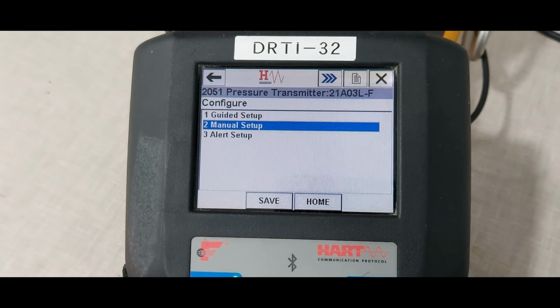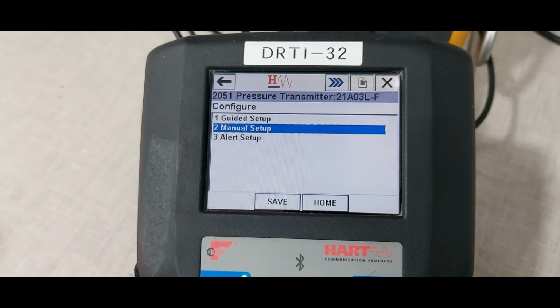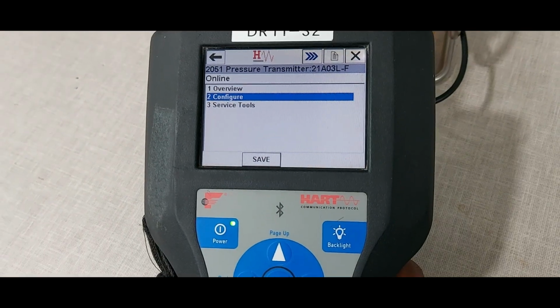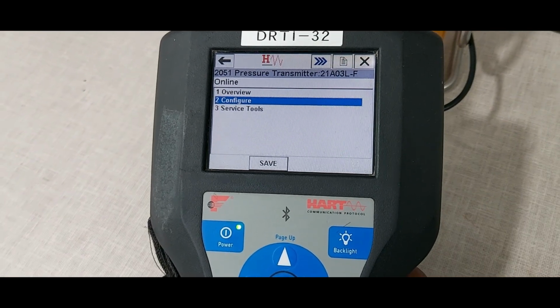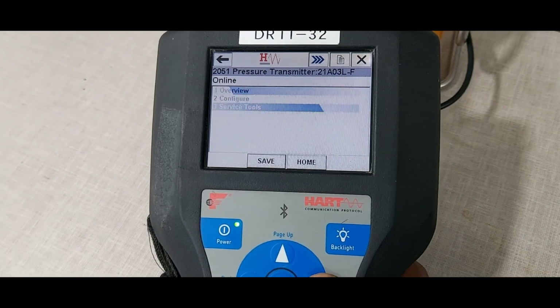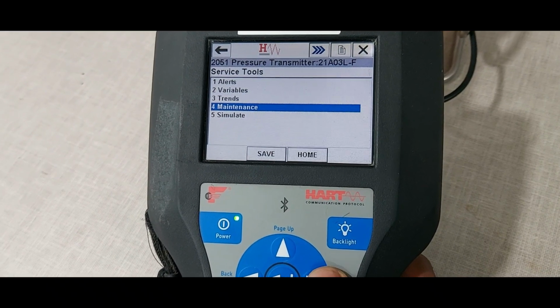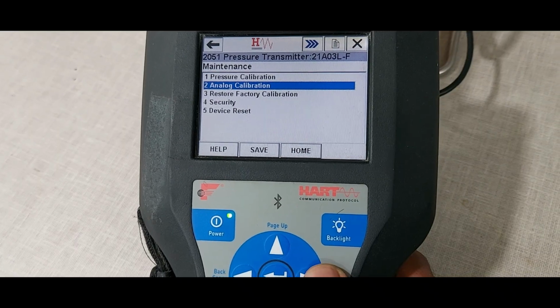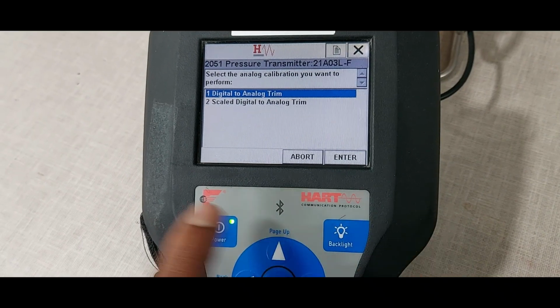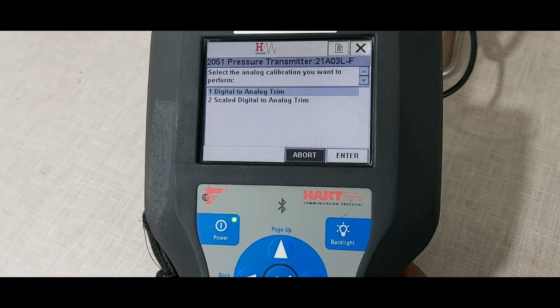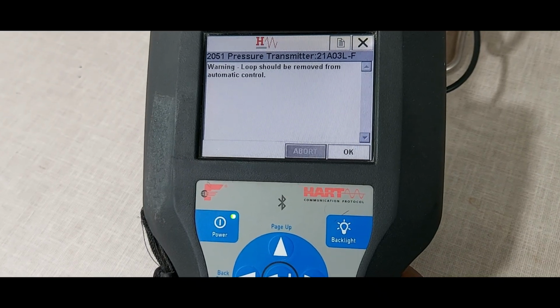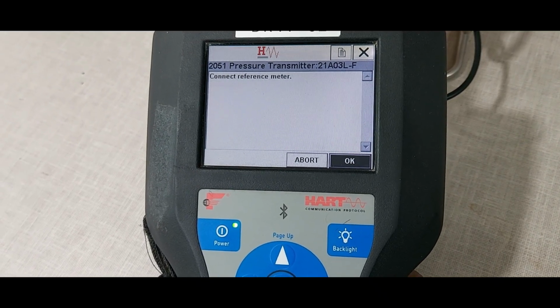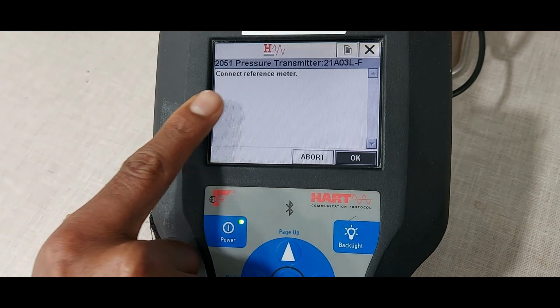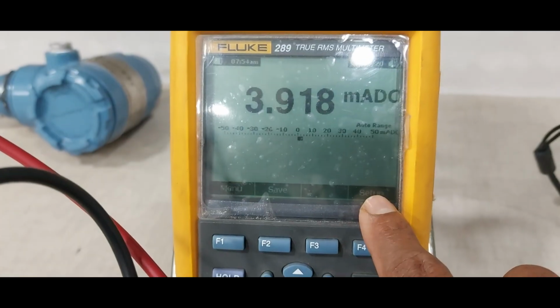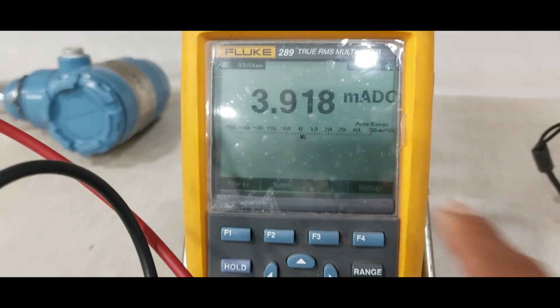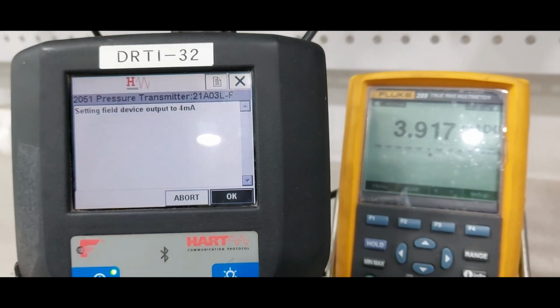Next we are doing the calibration procedure. First we are performing the DA trim calibration. Select the service tools and maintenance and analog calibration. Okay, digital to analog trim. Enter. Then okay. Okay, connect the reference meter. Reference meter already connected. Then okay.